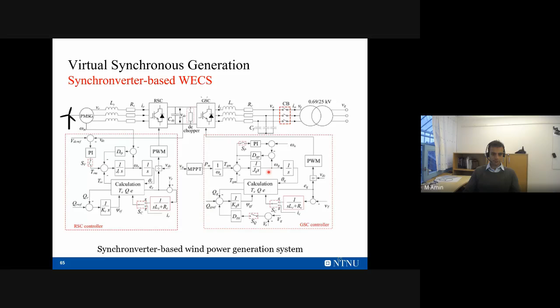We also carried out impedance-based analysis with this control. If you compare the impedance characteristics for this synchronverter controller, we see that it's like an RL, so more like a synchronous generator behavior, while with the standard controller the impedance characteristics are more complex. Here, the pink and blue circles are for the standard control, and the green one is for the synchronous generator control. We discuss this in more detail in this paper. So we see that it has some better properties.